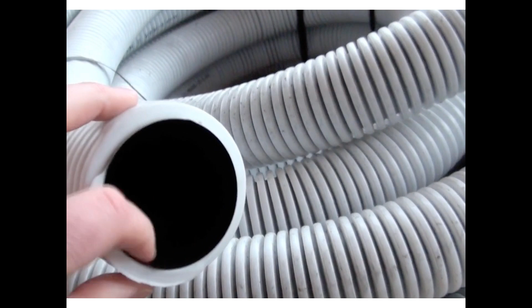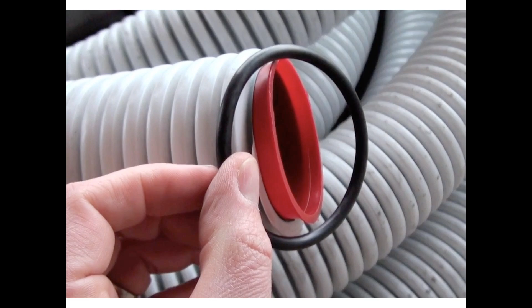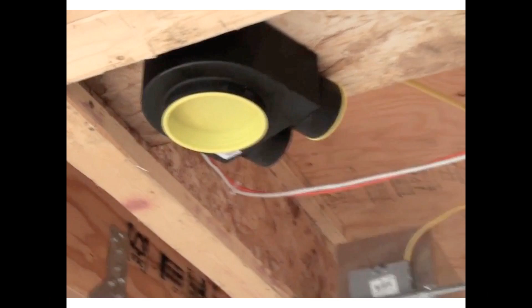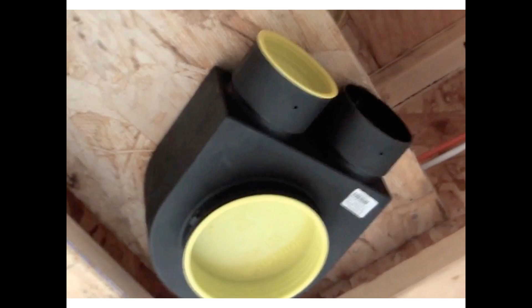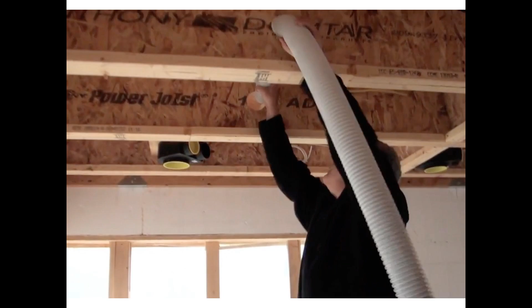There's another sequence showing how it all plugs together. A little rubber O-ring is inlaid into the grooves, allowing the pipe to plug into the manifold or the diffuser box in the ceiling. This connector piece lets you fuse two pipes together if one isn't long enough. The diffuser box in the ceiling has two inlets and is made from plastic—the Zehnder one I showed was metal, but it's the same concept. The opening on the bottom, currently concealed, is where the diffuser goes later. You basically run it through, plug it in, and walk away—that's how basic it is to get ventilation to and from a space.